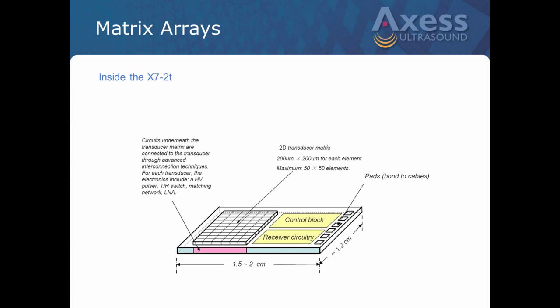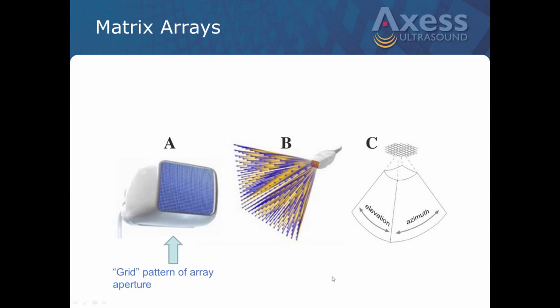One of the things Philips does with this particular probe model is there's an ASIC chip that's actually embedded in here with the array. And that is programmed at the factory, and that actually controls the send-receive signals and other parameters of the probe, and it is unique to each probe and array. First one of its kind that I've ever seen. So it's all embedded here. You can see the size is very small, 1.5 to 2 centimeters, 1.2 centimeters in width. Cabling comes in here, and again, this is your array. It uses very advanced electronic controls to actually control the firing and receive sequences.